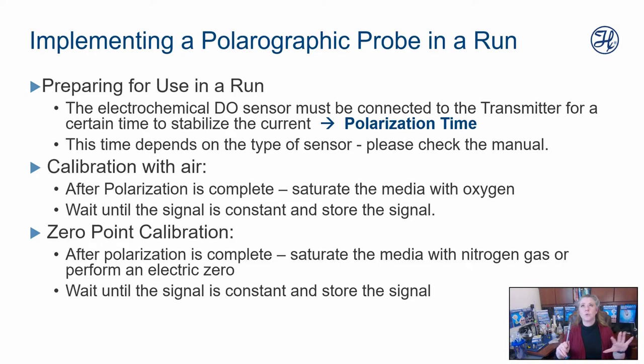Different manufacturers have different polarization times. Hamilton's happens to be the shortest I've ever heard of, 2 hours. There are other probes out there that require up to 10 to 12 hours of polarization. And if you do not let it have its full polarization, it is not stable. I'm going to go into that in a second. It actually doesn't have to be in liquid. Usually what people do though is they shortcut. So I say in liquid.